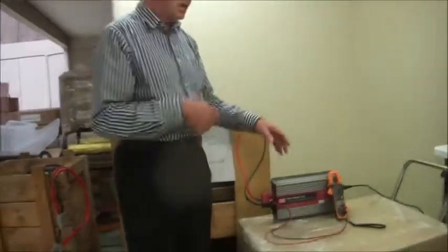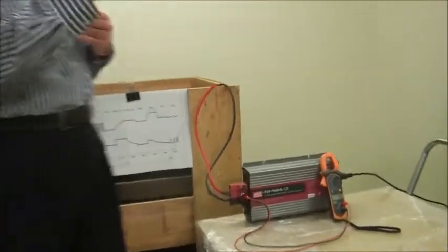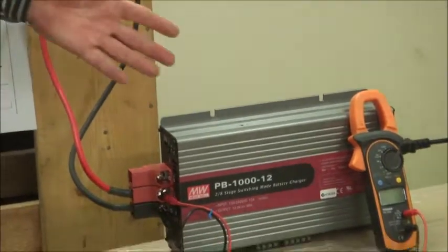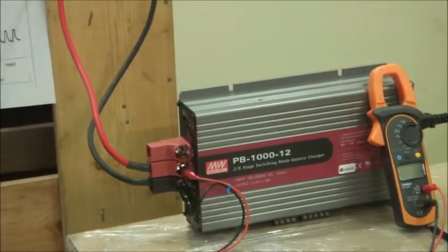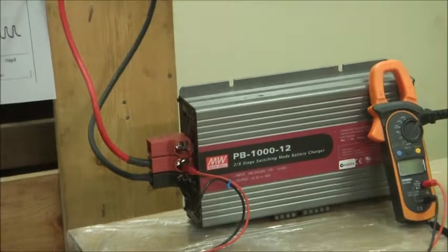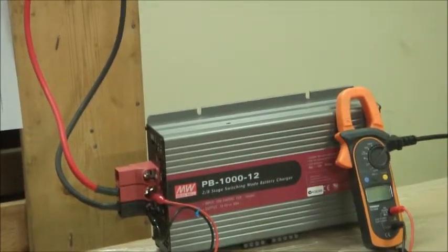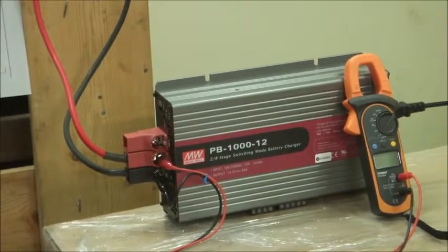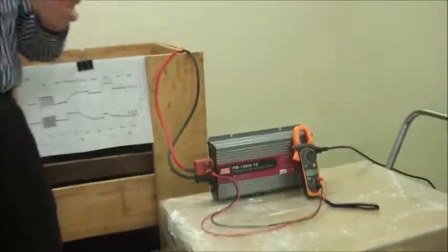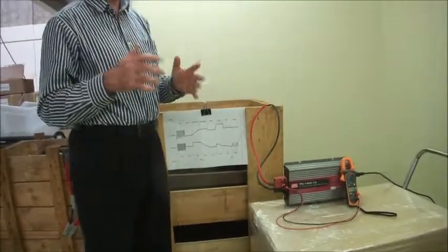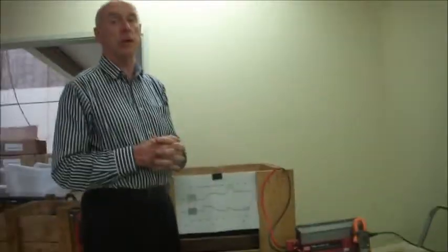This type of charger, even if it takes a little bit longer to charge. Even though, for example, it's a 650 amp hour battery and the charger according to the specification says that it's only good for a 170 amp hour, it won't hurt the battery. All it will mean is that you just have to charge it for a longer period of time, and that doesn't matter. You won't hurt the battery, but it will actually replenish the battery and bring it up to full state of charge.